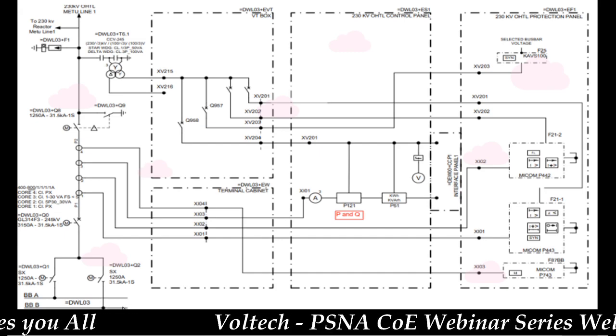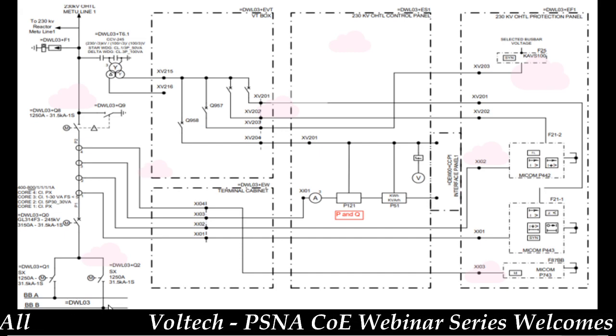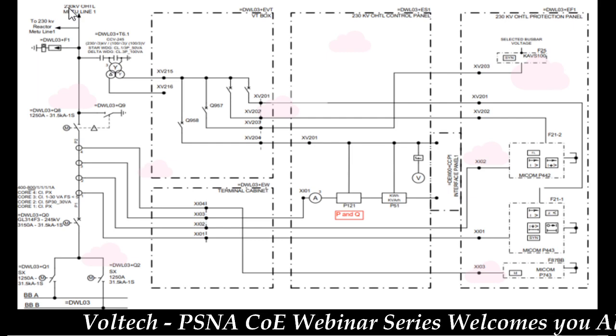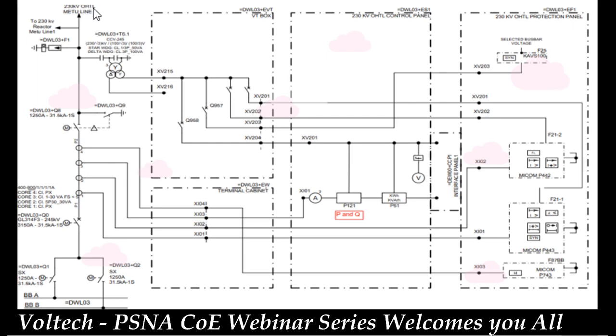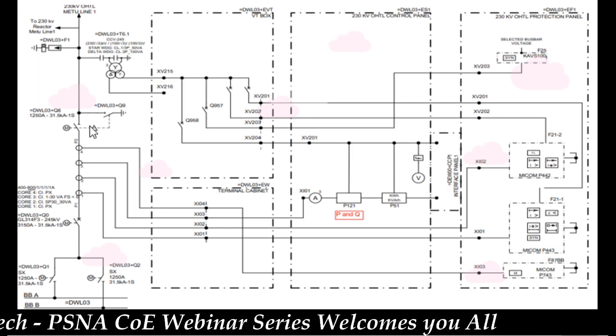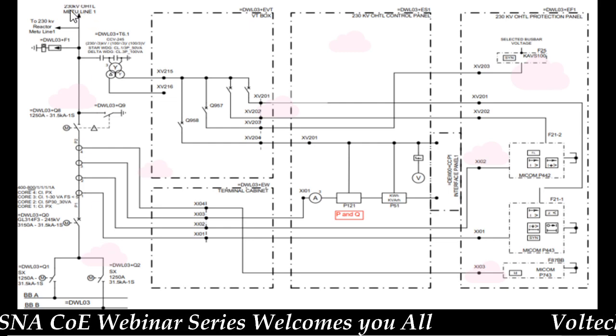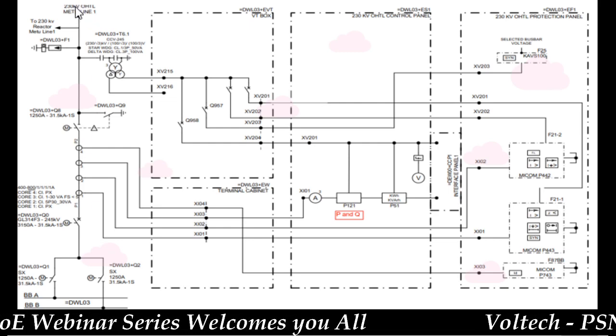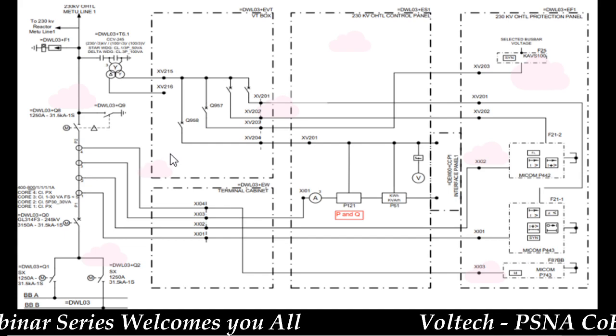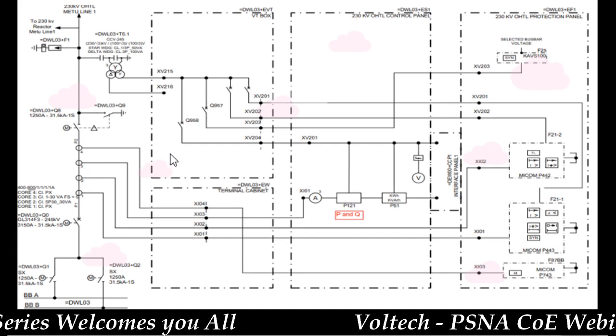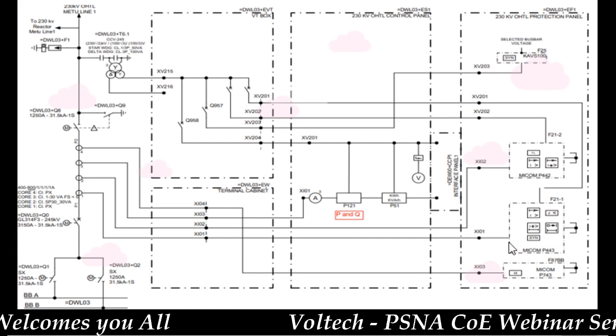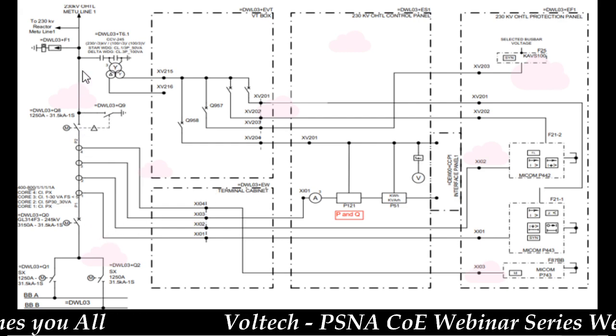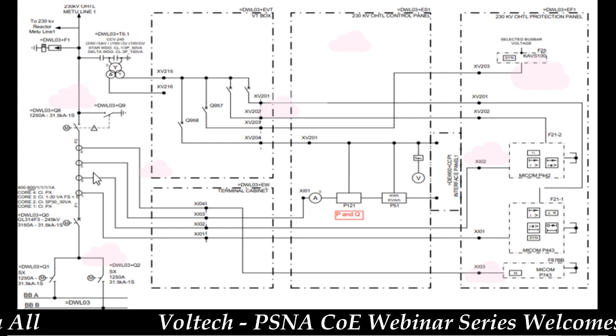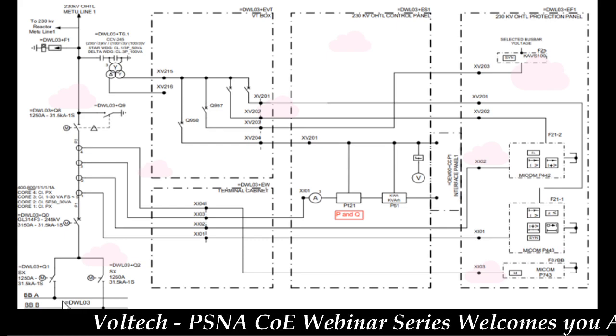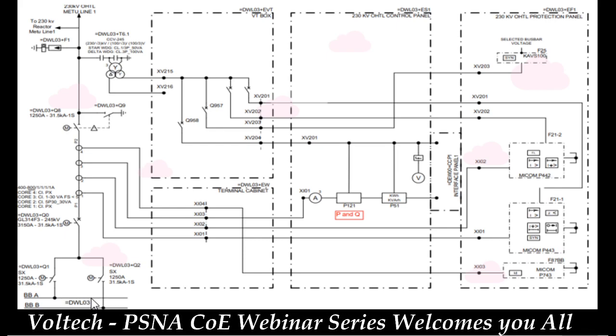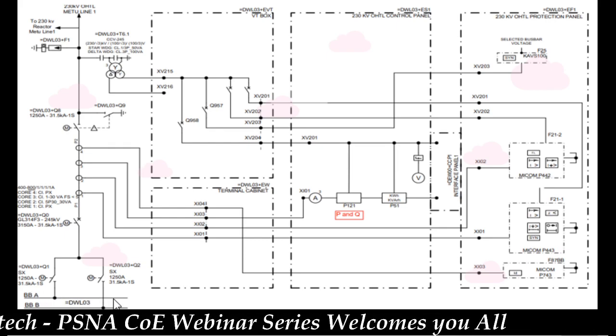So in the field we can find 2 bus bars. This is a 230 kV system. It's mentioned clearly here, 230 kV OHTL METU line. That means the name of the line and the kV level. So in the construction of the SLD, we already saw the system voltage. First we have to find the system voltage. So here the system voltage is mentioned clearly, and the type of arrangement is double bus. This is the double bus, bus A and bus B.